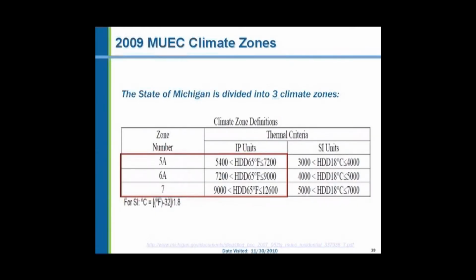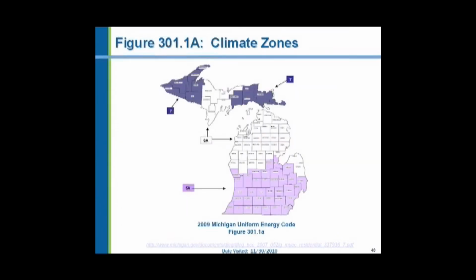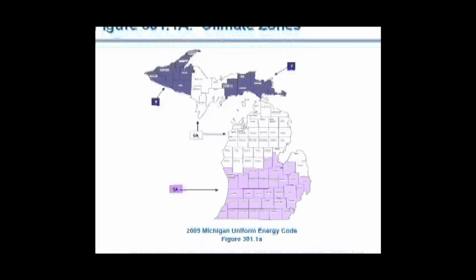On the Michigan website, they have detailed the heating degree days for each of the three climate zones that occur in the state of Michigan: climate zones 5A, 6A, and 7. And they further zoomed in on the state on the website to show the counties in more detail. And there's climate zone 6, which intrudes itself into the middle of the Upper Peninsula. Notice around Saginaw Bay, where instead of going north to get to a colder climate zone, you go west.